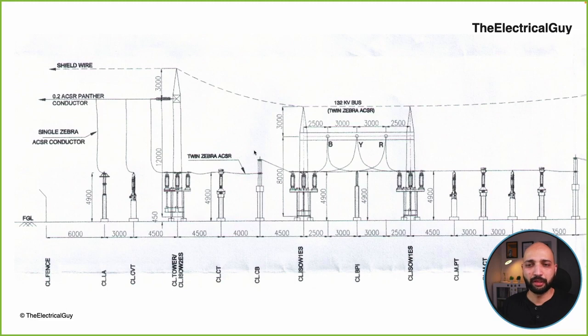So this is the circuit breaker that we saw. This is again an isolator provided. Now in order to understand this arrangement, why isolator is provided here and here as well, we need to understand the single line diagram, or it is also called as SLD. And it is also important to understand the bus bar scheme that is used, whether it is double bus bar or whether it is 1.5 breaker scheme. That is important to know.